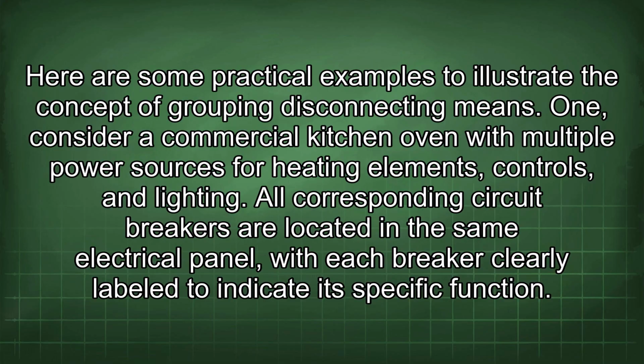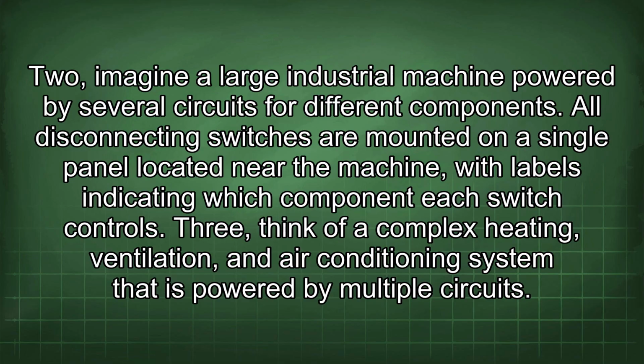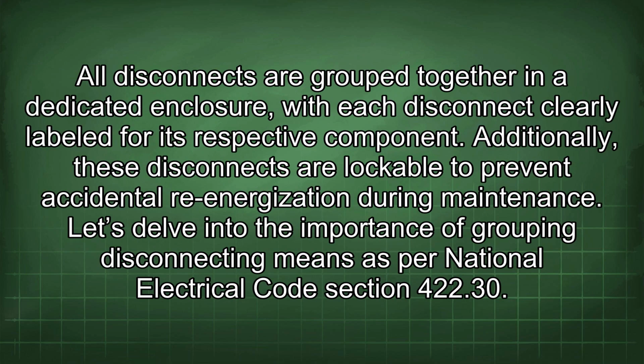Here are some practical examples to illustrate the concept of grouping disconnecting means. 1. Consider a commercial kitchen oven with multiple power sources for heating elements, controls, and lighting. All corresponding circuit breakers are located in the same electrical panel, with each breaker clearly labeled to indicate its specific function. 2. Imagine a large industrial machine powered by several circuits for different components. All disconnecting switches are mounted on a single panel located near the machine, with labels indicating which component each switch controls. 3. Think of a complex heating, ventilation, and air conditioning system that is powered by multiple circuits. All disconnects are grouped together in a dedicated enclosure, with each disconnect clearly labeled for its respective component. Additionally, these disconnects are lockable to prevent accidental re-energization during maintenance.